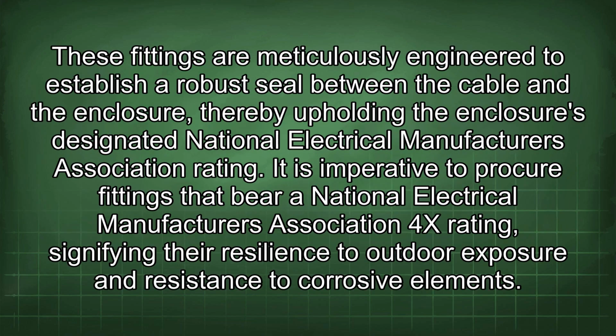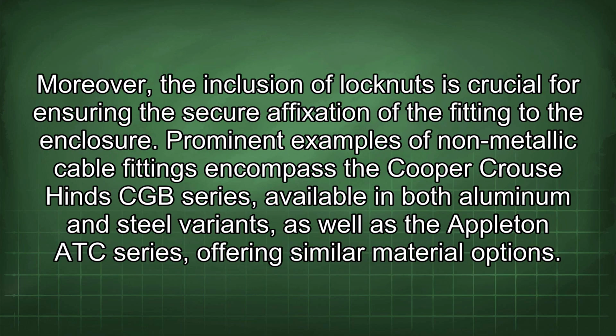These fittings are meticulously engineered to establish a robust seal between the cable and the enclosure, thereby upholding the enclosure's designated National Electrical Manufacturers Association rating. It is imperative to procure fittings that bear a National Electrical Manufacturers Association 4X rating, signifying their resilience to outdoor exposure and resistance to corrosive elements. Moreover, the inclusion of locknuts is crucial for ensuring the secure fixation of the fitting to the enclosure. Prominent examples of non-metallic cable fittings encompass the Cooper Crouse-Hinds CGB series, available in both aluminum and steel variants, as well as the Appleton ATC series, offering similar material options.